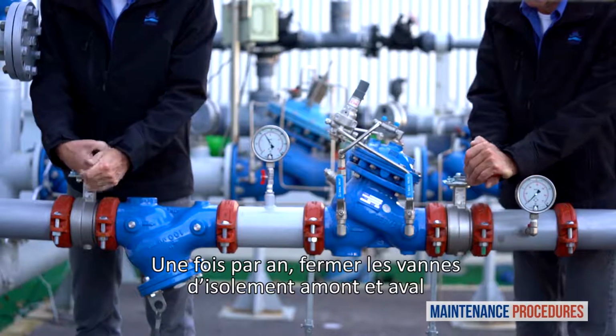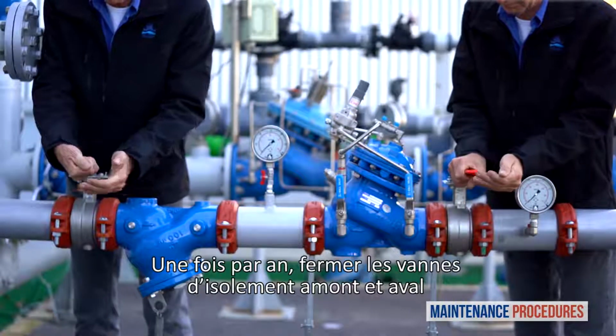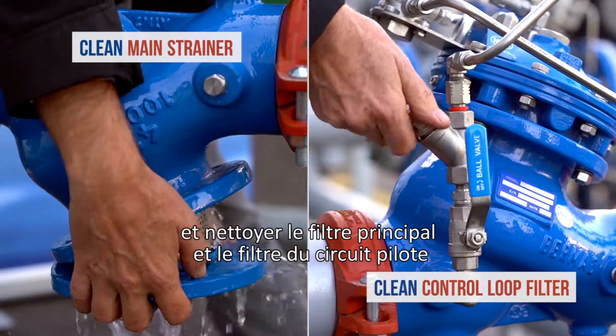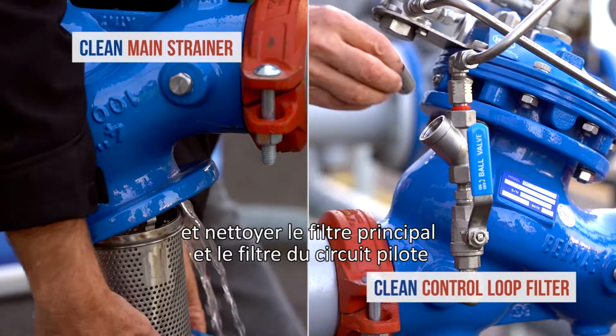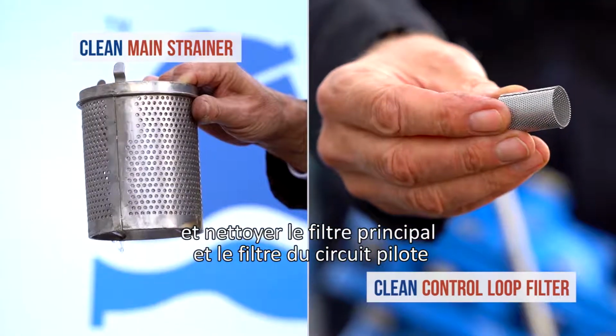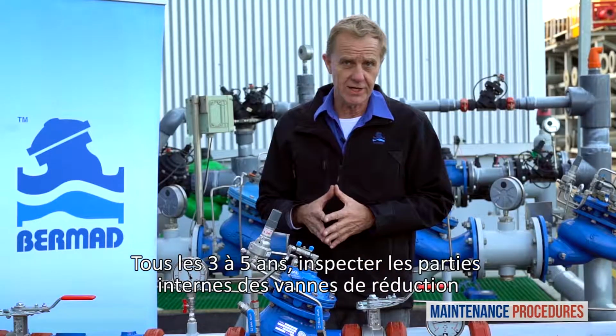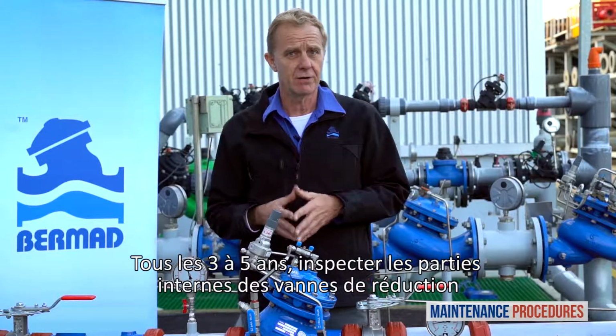Once a year, close both the upstream and downstream isolation valves and clean the main strainer and the valve control loop filter. Every 3 to 5 years, inspect the internal condition of the pressure reducing valve.